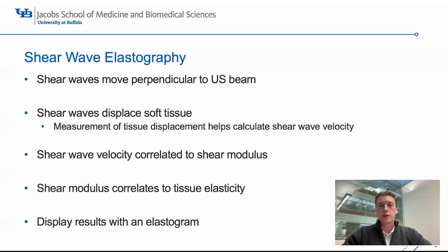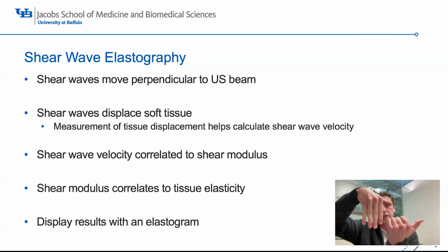First off, you get shear waves that are moving perpendicular to your ultrasound beam. So that acoustic radiation force impulse that Nightingale and Sarvazian worked on is going to come off perpendicular. Your ultrasound beam is going to go down into the tissue and the shear waves, you can imagine, are making a right turn and going 90 degrees to that beam. That creates a shear force on the tissue it's moving through, and the shear waves are going to displace the tissue.